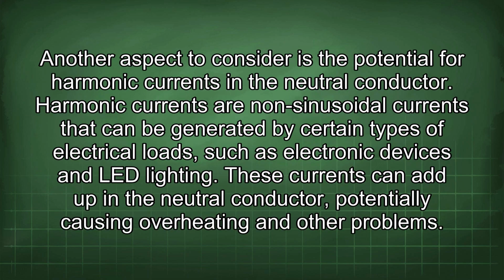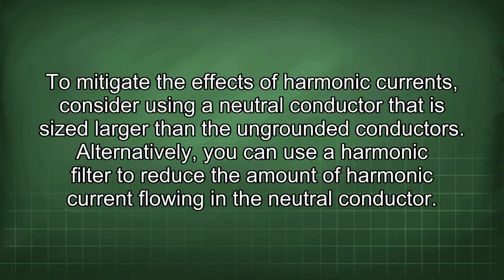Another aspect to consider is the potential for harmonic currents in the neutral conductor. Harmonic currents are non-sinusoidal currents that can be generated by certain types of electrical loads, such as electronic devices and LED lighting. These currents can add up in the neutral conductor, potentially causing overheating and other problems. To mitigate the effects of harmonic currents, consider using a neutral conductor that is sized larger than the ungrounded conductors. Alternatively, you can use a harmonic filter to reduce the amount of harmonic current flowing in the neutral conductor.